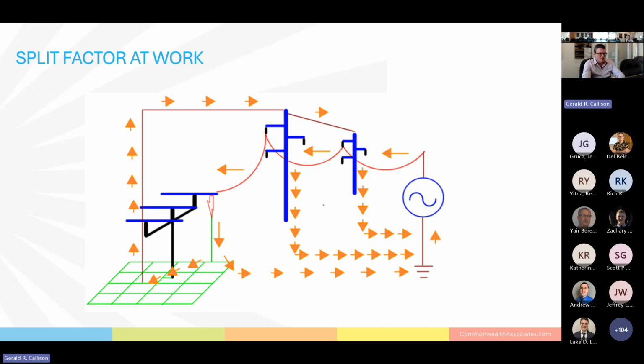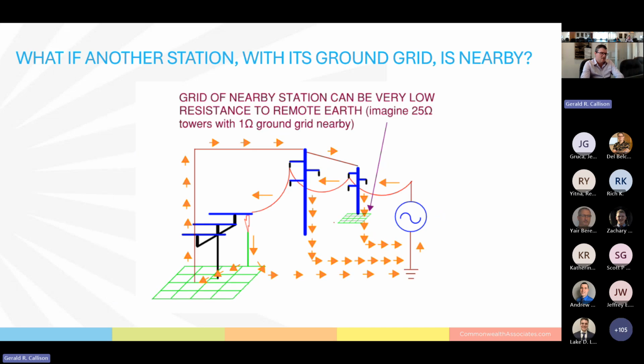Now, I said that 15 ohms would be a very low value that we would assume for a transmission tower, and a typical value for a ground grid might be 1 ohm. So 15, 25 ohms, that may be a lot, but when you put dozens of towers almost in parallel, aside from the small resistance of the shield wire, then that lowers quite a bit, and split factor can be quite significant.